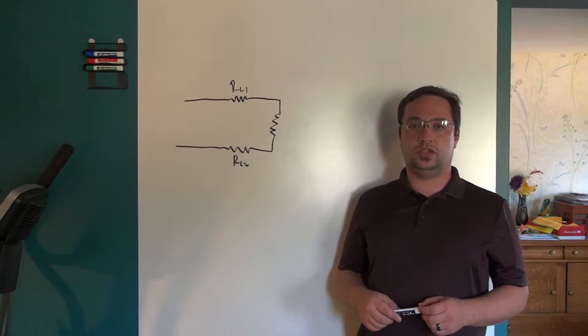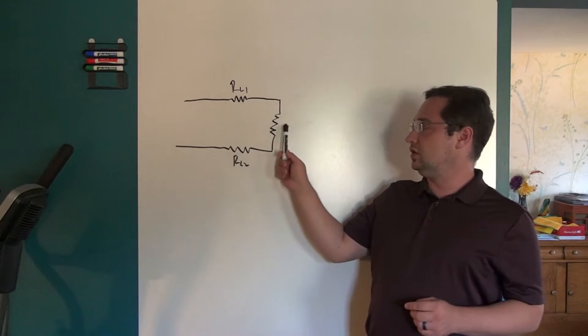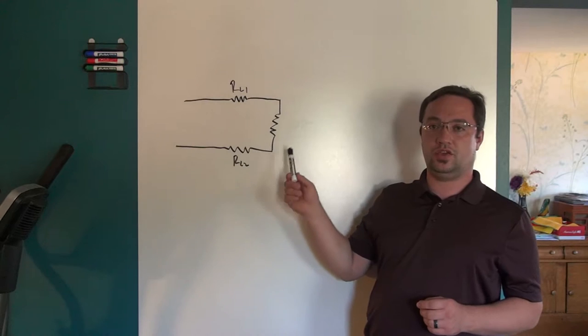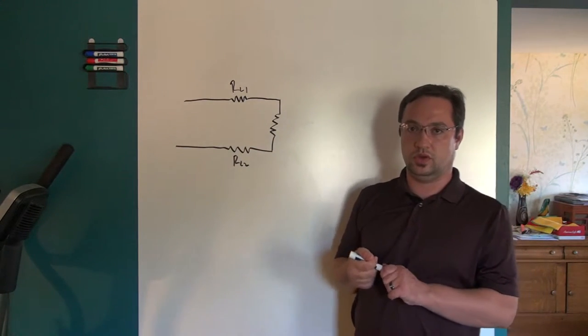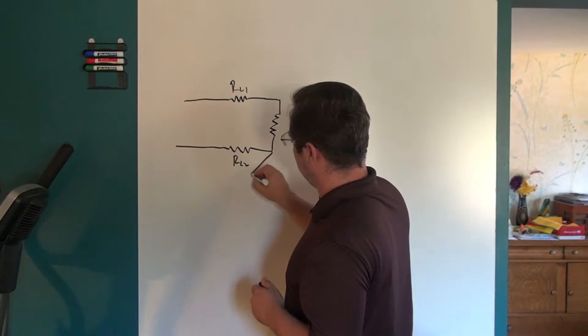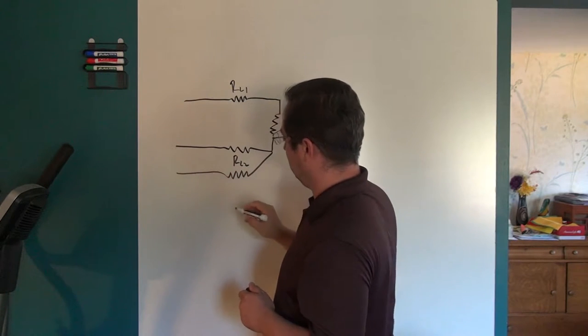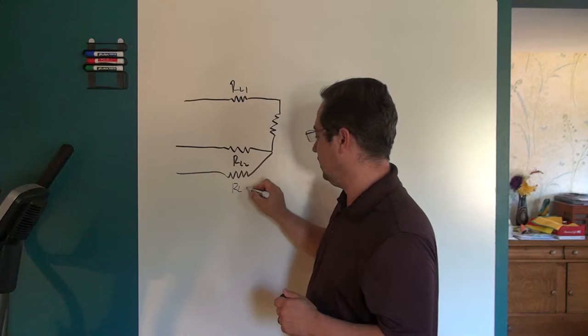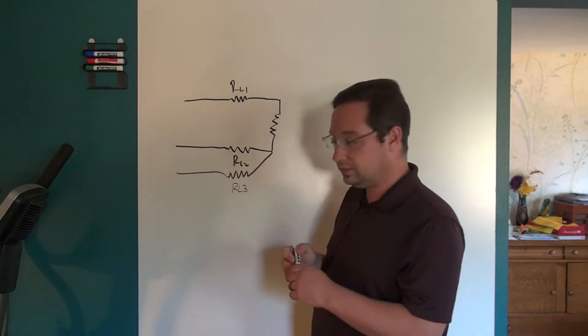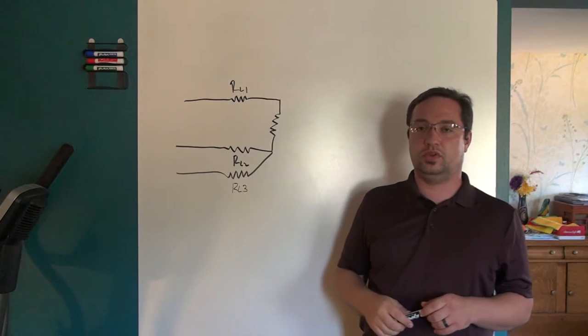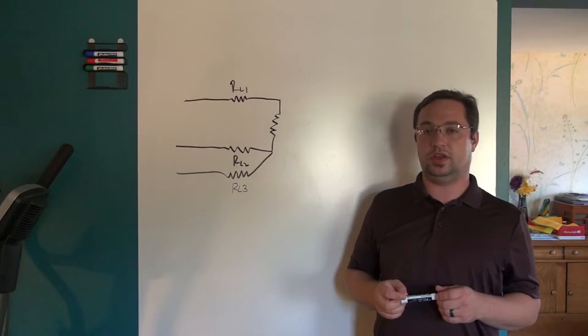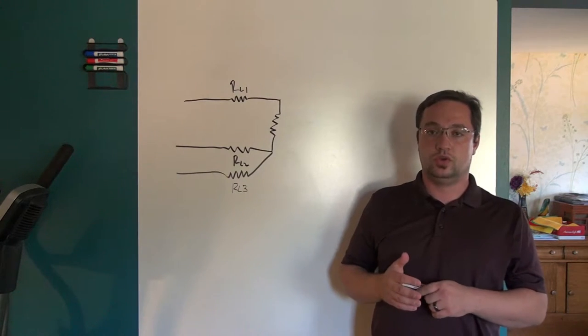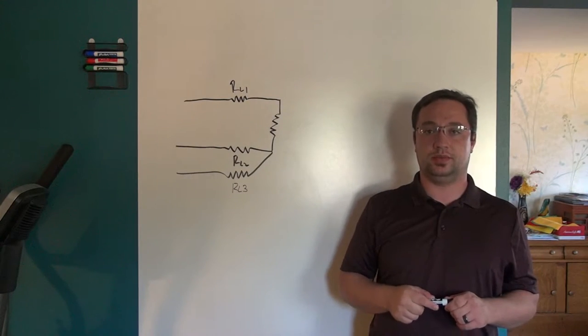The first way to deal with this kind of inaccuracy is these RTDs come in a three terminal combo. So what you have is another lead that's broken out like that, and then this will be RL3. This three lead combo, there are two basic strategies for taking a measurement with it, and those strategies both work to reduce the error of how much resistance you actually read across the element.